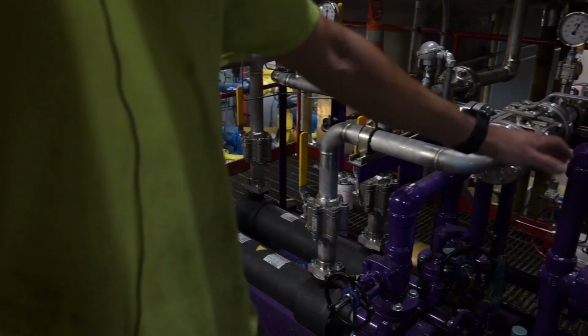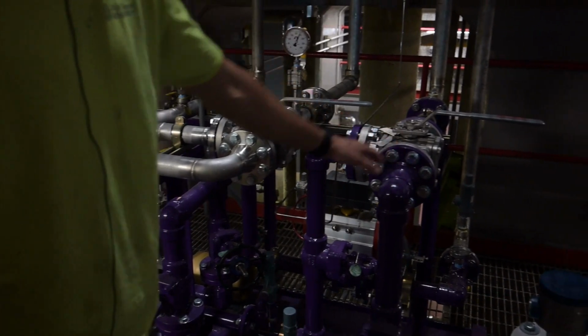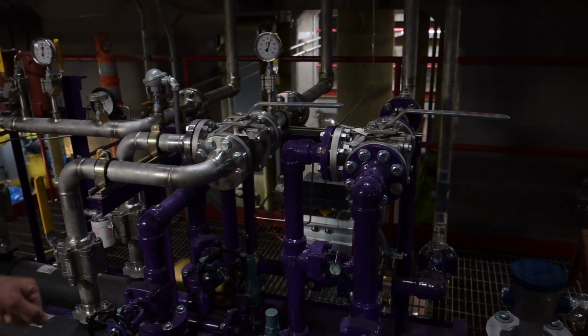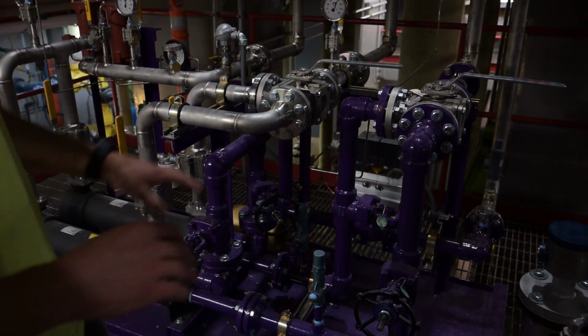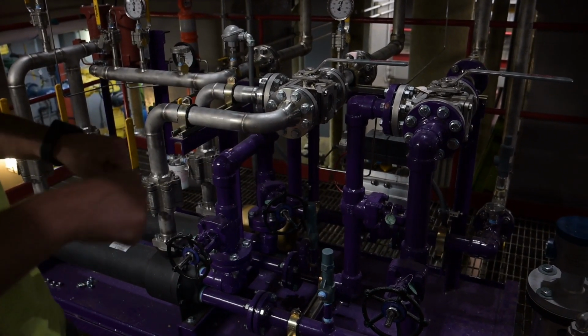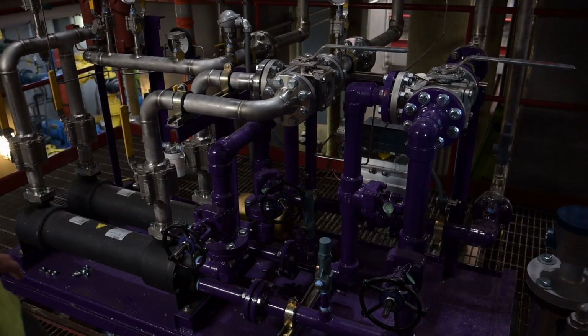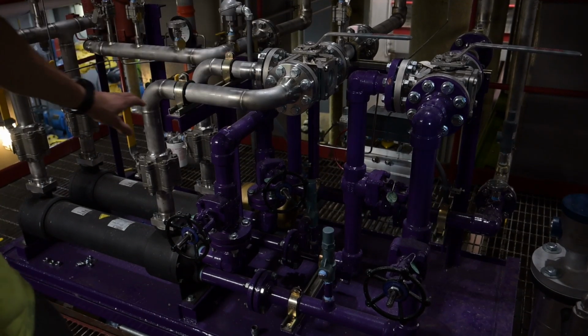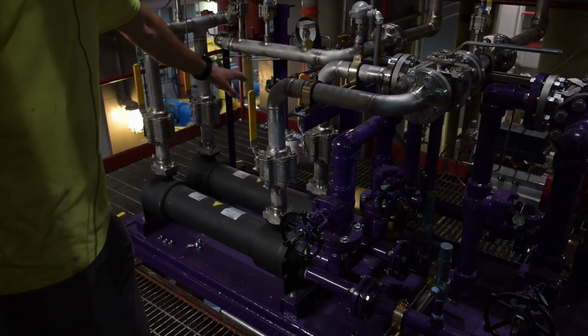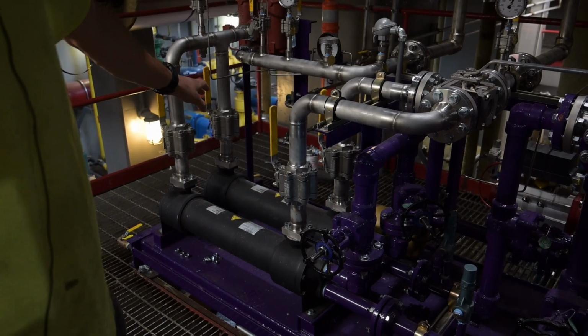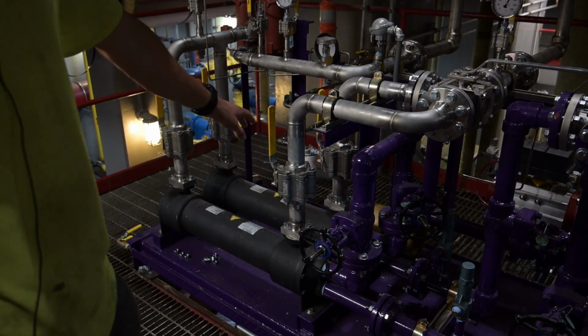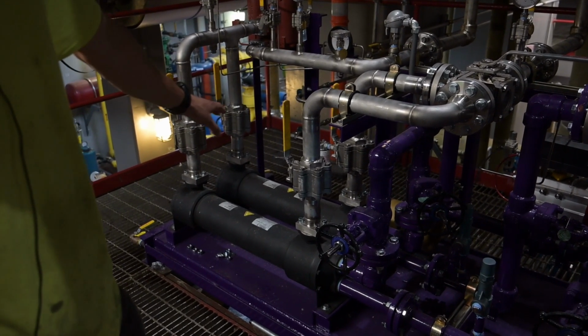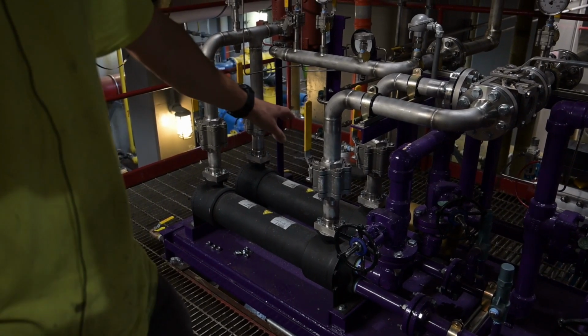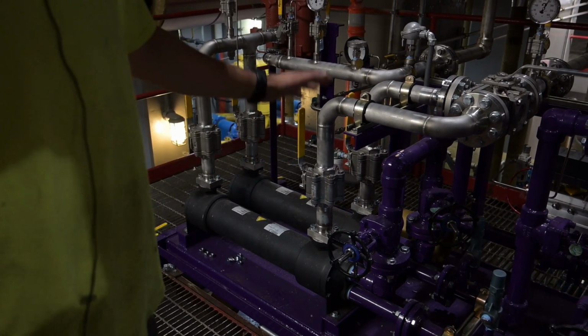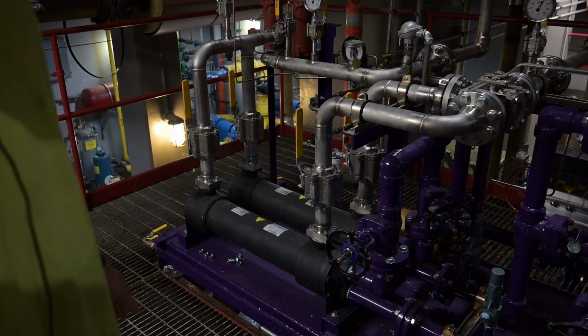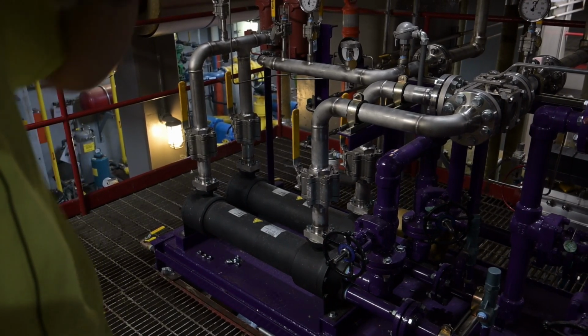And then same with the cooling water to the lube oil heat exchangers. So we want to switch these over at the same time if we need to. Also very important, if you are going to switch it over, make sure that you have your isolation valves opened up. If you switch it over with an isolation valve closed, the equipment's not going to get any oil. It's just going to go out of the relief valves up on the turbine.